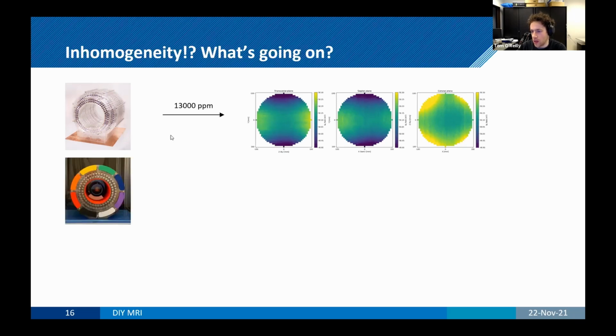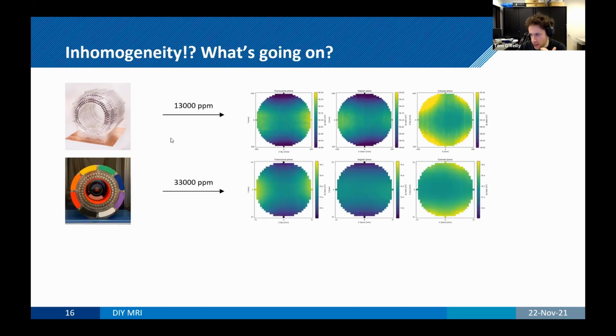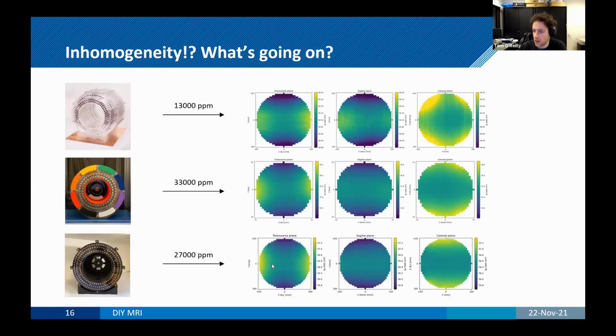And if we look at some of the other magnets that we've built since then, we see the exact same field pattern. This is an 87 millitesla wrist magnet that we constructed. Again, the homogeneity for all of these is supposed to be less than 1,000 ppm, but it always comes out way worse. And again, z squared minus y squared. This is a head-only system that we built, asymmetric, so it's curved at the back. So it's a somewhat different design from our conventional way of doing things. And again, we get exactly the same field pattern in our magnetic field plots, z squared minus y squared.